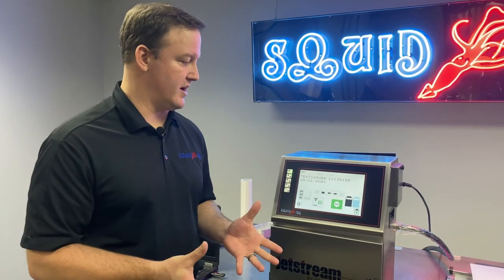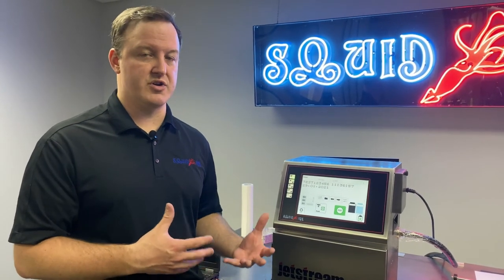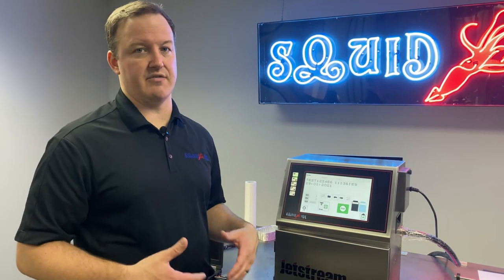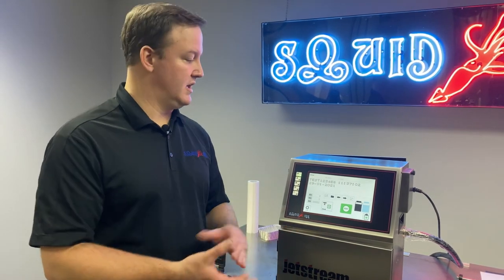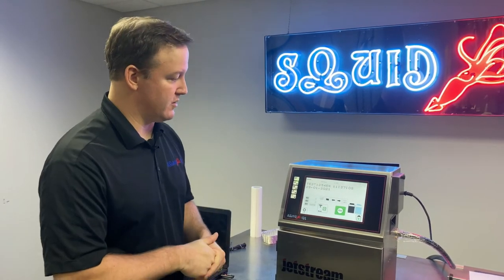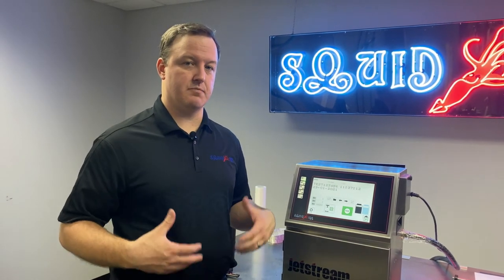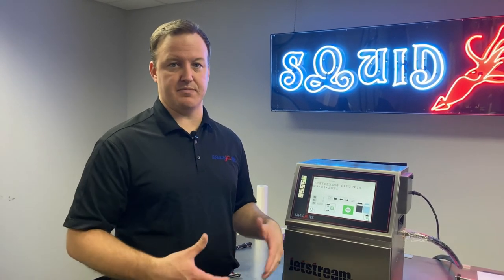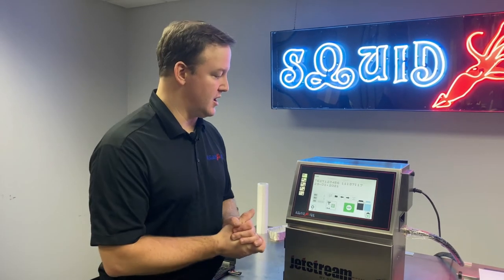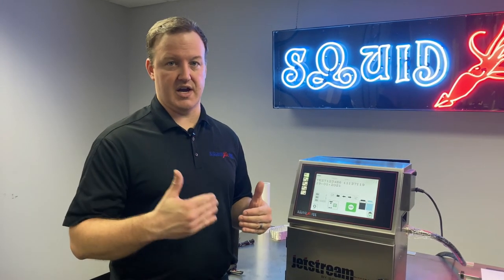But before we do that, we'll just discuss the scenario in which we would notice that the system is having a tough time getting makeup out of the cartridge. And that's going to be related to the viscosity of the fluids in the system. So what will happen is, in this scenario, if we're having trouble managing the viscosity of our fluids, we're not able to get makeup into the tank, our viscosity is going to climb higher and higher. The fluids are going to get thicker and thicker.